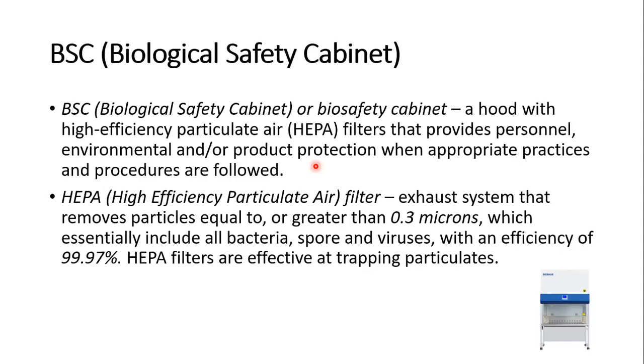So first of all, let's define what is BSC or Biological Safety Cabinet or simply Biosafety Cabinet. BSC or Biosafety Cabinet is a hood with high efficiency particulate air or HEPA filters that provides personnel, environmental, and or product protection when appropriate practices and procedures are followed. Biosafety Cabinet is an engineering control as a form of mitigation strategy. Regardless of what type of biosafety cabinet, you can always find a HEPA filter.